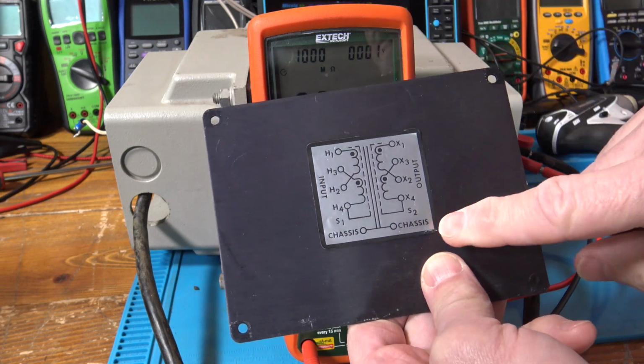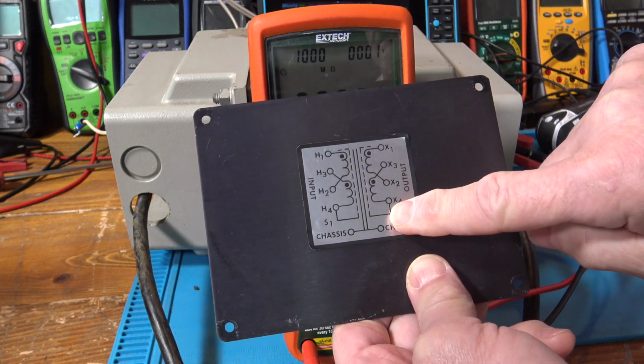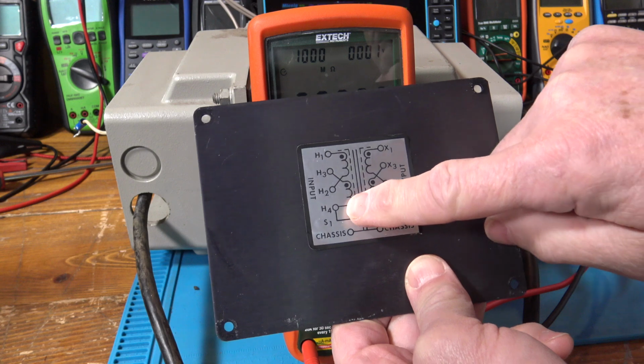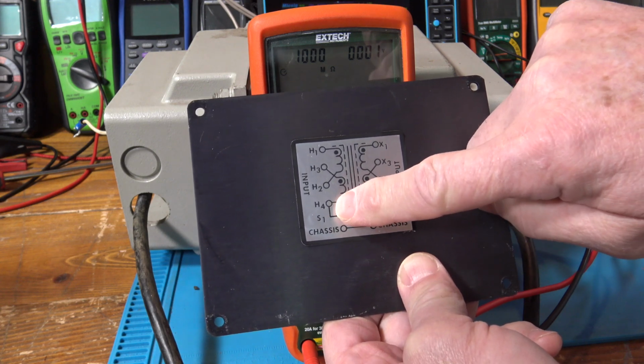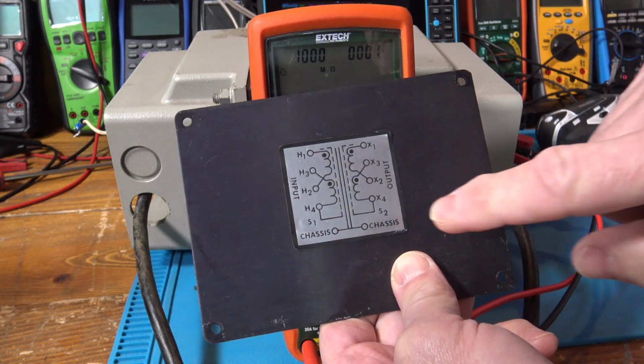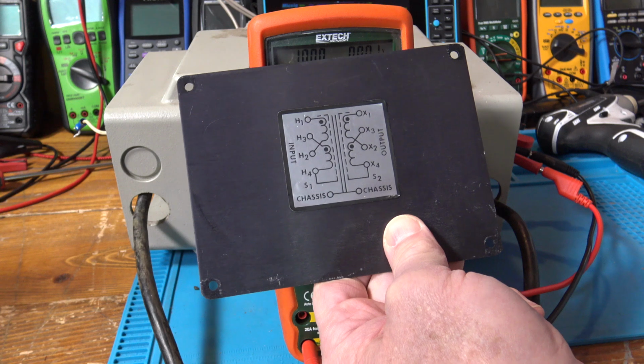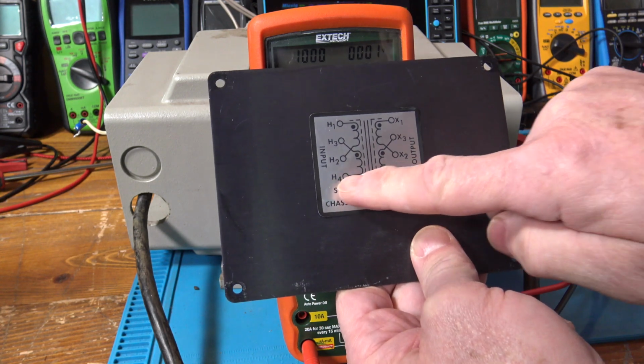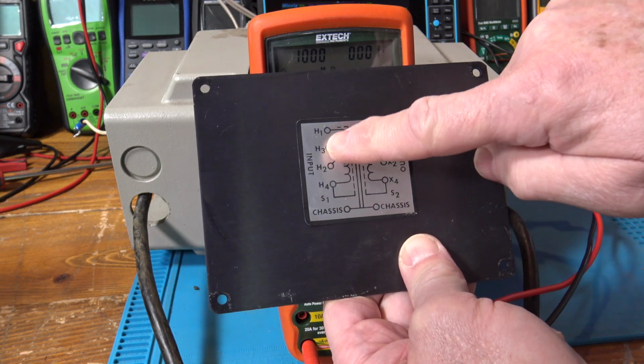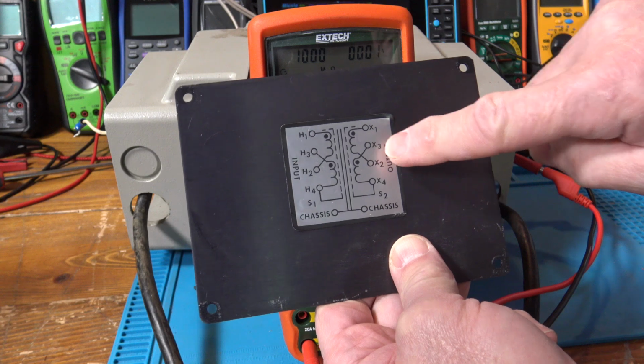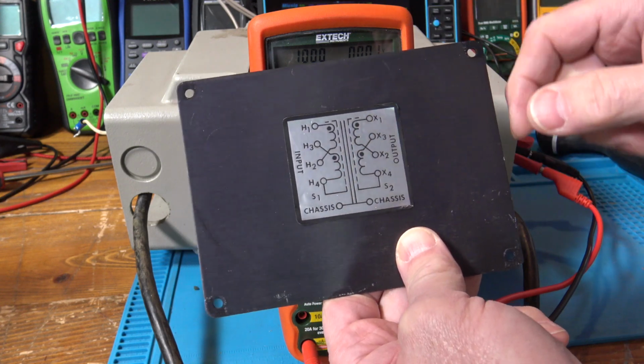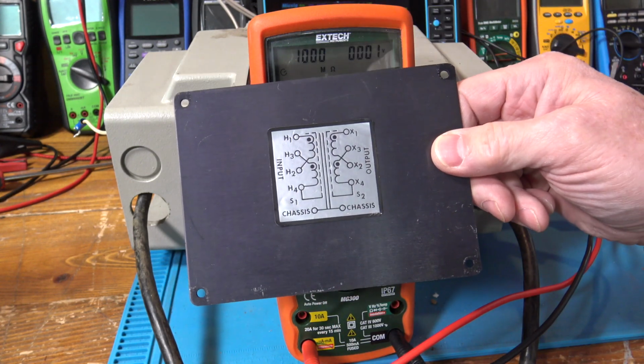So that's great, so it was that screen - that wire tying the screen terminal to chassis on both sides. It was giving us that ohmage. Now, when I went right across here, they were shorted, but when I went from H3 or X3, it would go through the winding, giving us some impedance at this HiPot.